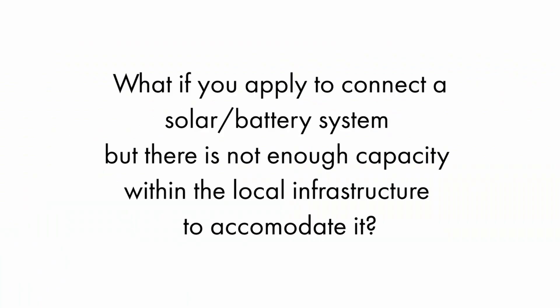The DNO will know that in a local network there's a certain amount of excess capacity within the infrastructure to account for voltage rises. For example, they'll know that if there are say 100 kilowatts being exported to the local grid, that'll cause the voltage to hit the 10% ceiling. If the local infrastructure isn't strong enough to take the full capacity of the system, they'll then go back to whoever submitted the application and let them know the largest capacity that can be installed without paying for upgrades to the local network. Often this will include things like generation and export limitation.